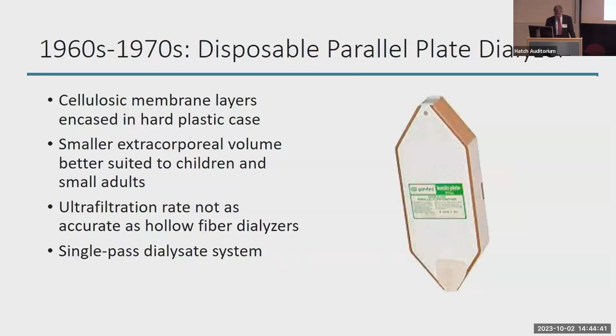But it was an advance over the tank system because it was a single pass system, so you didn't have to change the dialysate and row it in the middle of a treatment. So really the landmark change in terms of our membrane configuration technology came with the hollow fiber, and Juan kind of introduced this structure a little while ago. So this occurred primarily around the mid-1960s and was ultimately dependent on advances in the manufacturing process for these membranes. There were advances in extrusion technology, as opposed to making sheets of membrane. They were able to make them into capillary tubes, and that allowed for the replacement of these coiled and flat membrane dialyzers with hollow fibers, the major advantage of which was a much greater surface area in a smaller package.